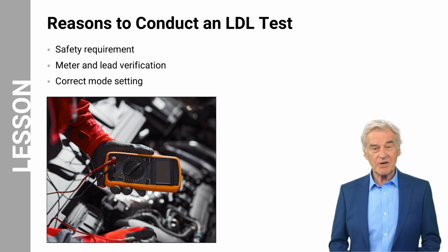Next is meter and lead verification. Performing an LDL test helps ensure that the HV meter and its leads are functioning correctly. This is important because faulty equipment can provide inaccurate readings, leading to potential safety hazards.